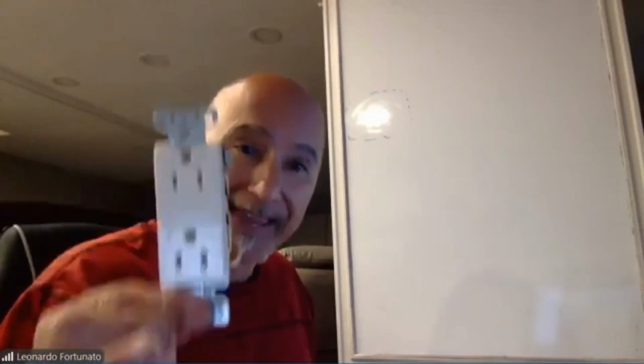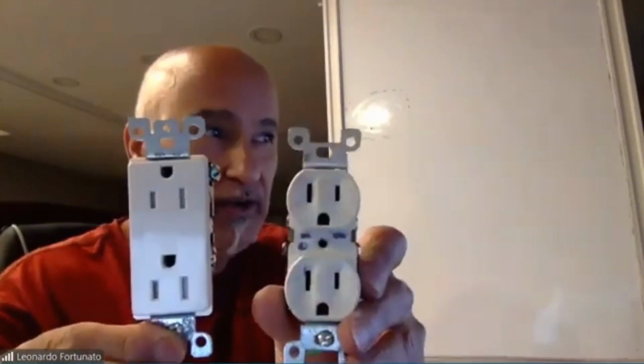Now that we understand a bit more of the anatomy of a regular receptacle, again, when we look at it, this is a Decora - it's exactly the same as this one here, traditional, just the style changes. Again, the neutral is always the long slot, silver screws. When we look at this receptacle here, the neutral is the long slot, but it's also T-shaped because, years back, a 20 amp receptacle looked exactly like a 15 amp receptacle.